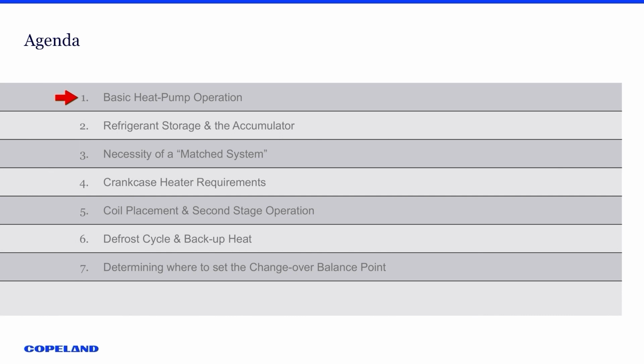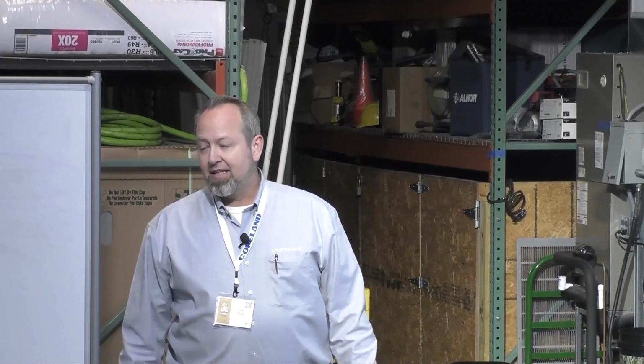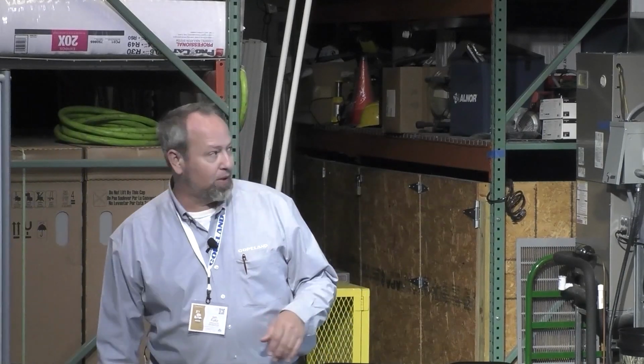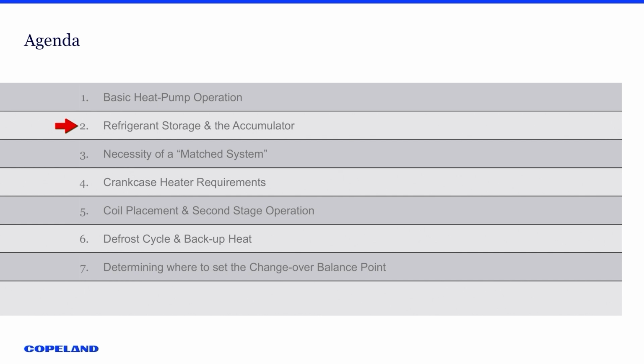The agenda for today: we're going to go over the basic operation of heat pumps, and then the parts and pieces that make the difference, parts and pieces that we need to understand so that when we get to the dual fuel piece of it, it all meshes and that second stage equipment, whatever that looks like, will function properly. Refrigerant storage and accumulator, the necessity of a matched system, I'll hammer that point home very hard. Crankcase heater requirements, coil placement, second stage operation, how that all works together, especially with a dual fuel. And then the defrost cycle and the backup heat, how those function in.